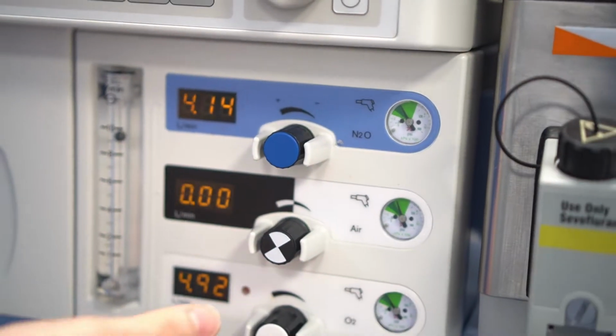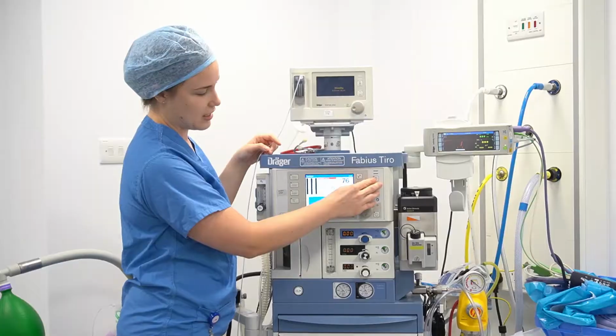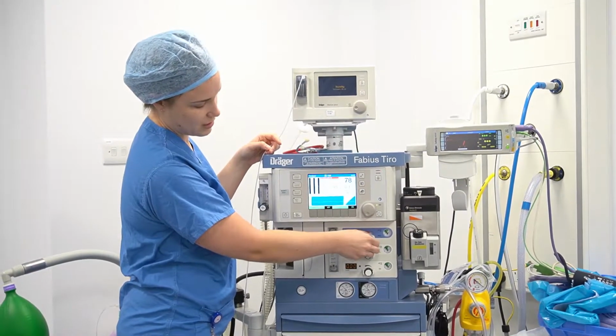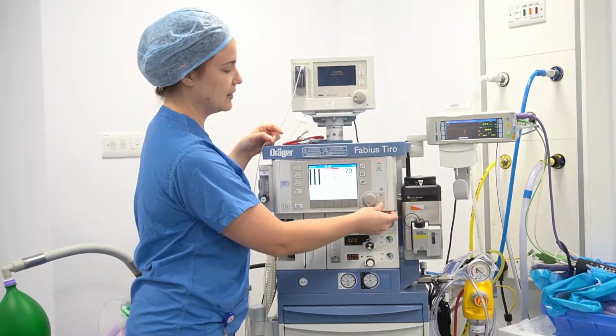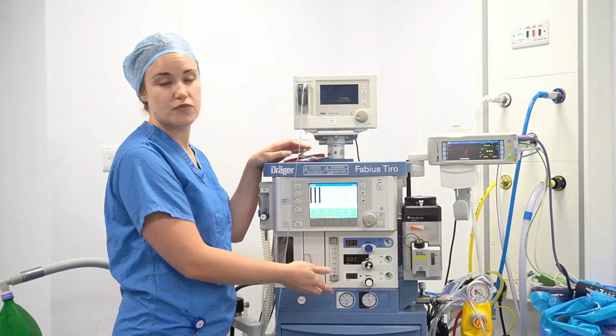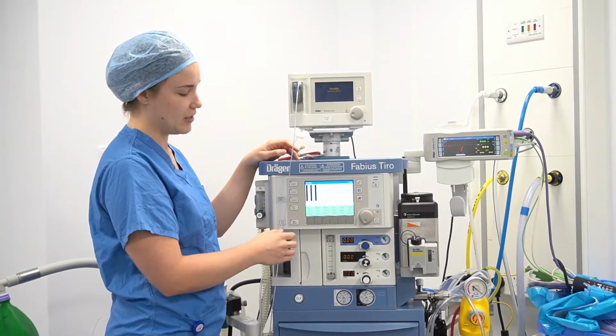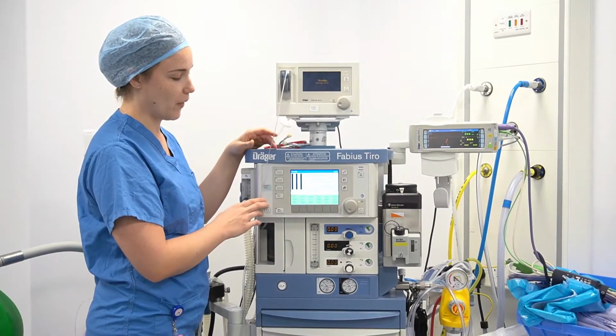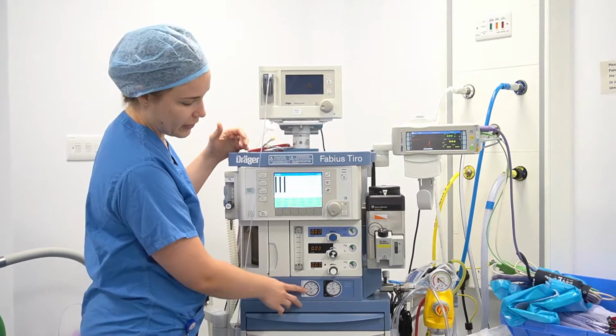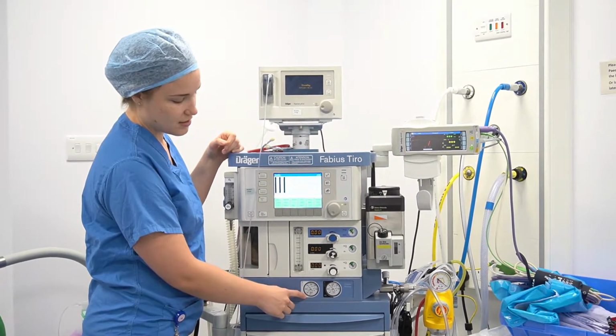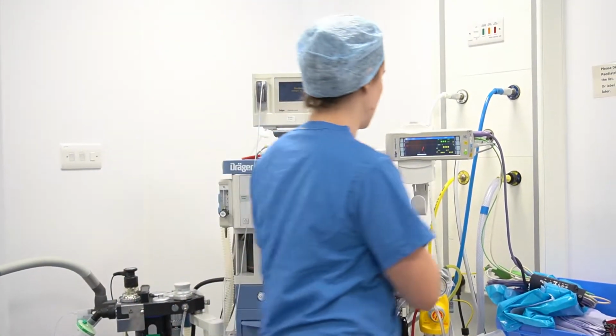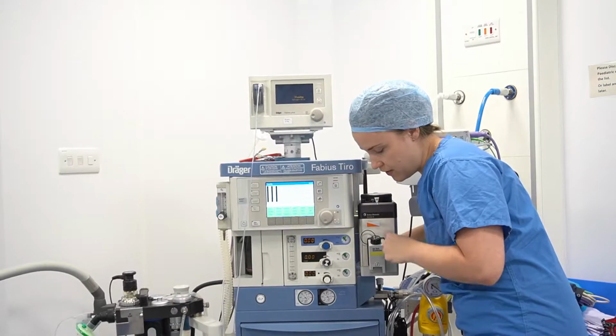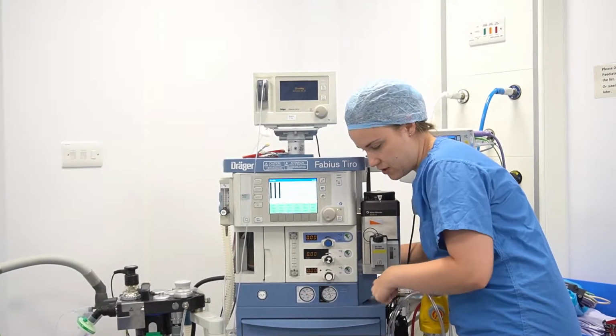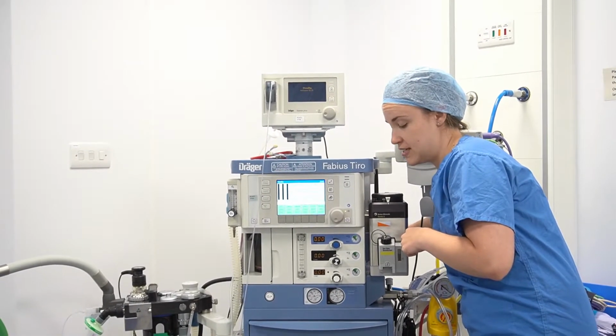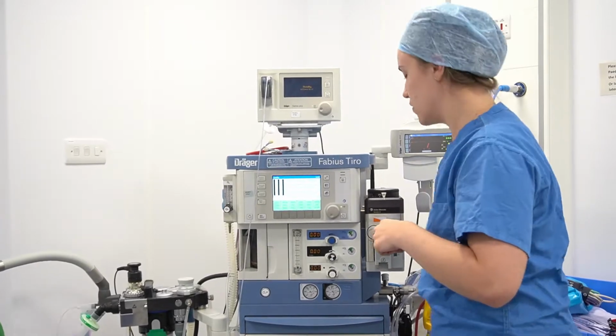And then as with any anaesthetic machine, any time you wanted to put on your nitrous without any oxygen itself, you can see here that it's not actually going to turn on. Okay. As you see, as soon as you put on your oxygen, your ventilator immediately goes into manual spontaneous ventilation. Okay. And then also, while you're here, we can check your cylinder pressure. So at the moment here, you can see these cylinders are on 0, and you can just check that by opening the cylinders at the back. And then you can watch your gauge pressure increase. You can see it increases to 1500. And then don't forget to close these again. So make sure they are tightly closed.